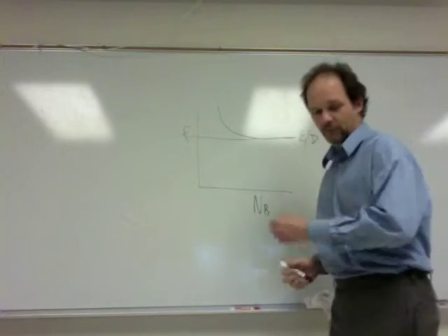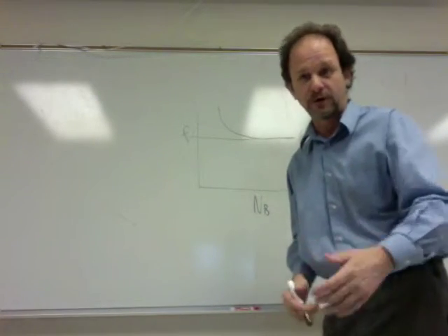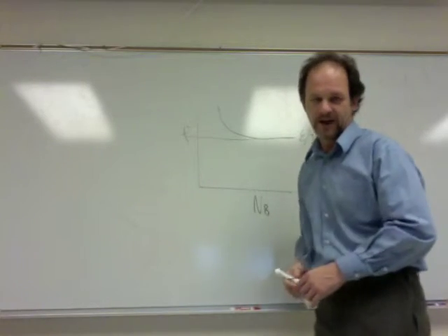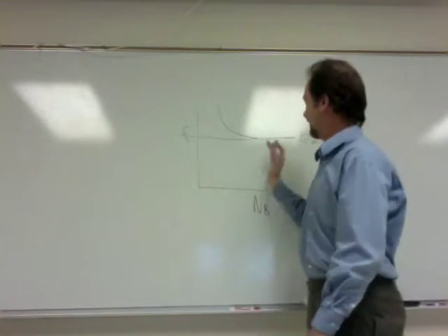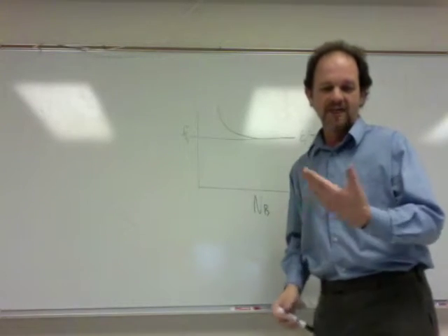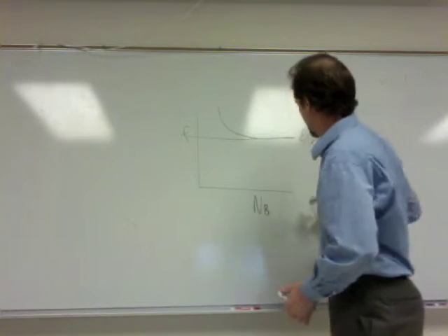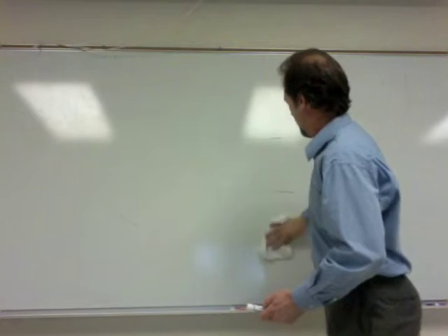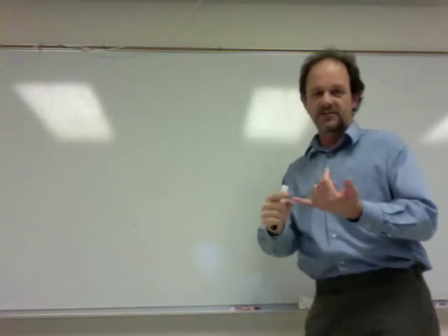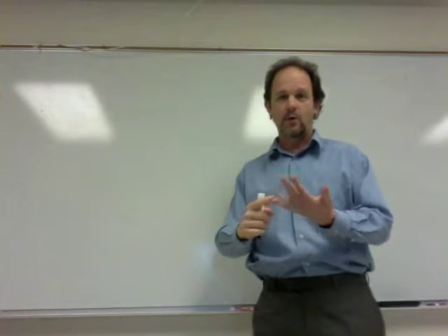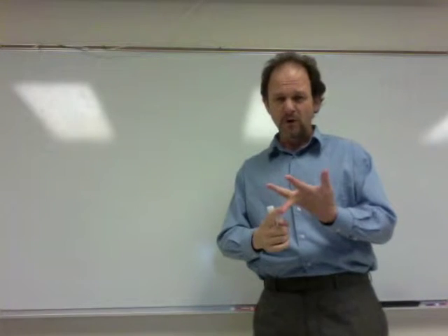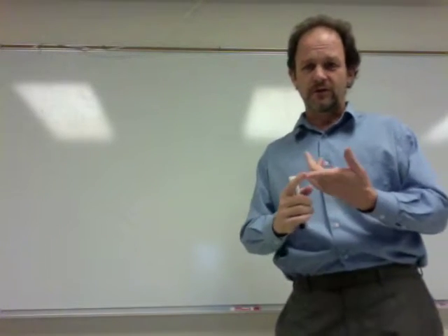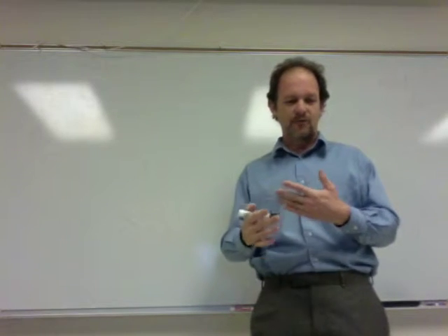You have to remember that 6 inches is 1/2 foot, and so your roughness for a cast iron pipe divided by 0.5 gets you your relative roughness. That gets you a friction factor, and then you can go to a calculator and do Bernoulli's equation with the inputs of what is the length in feet, what is the head available, what is the friction factor, what is the diameter of the pipe, and it should solve for you a flow rate.